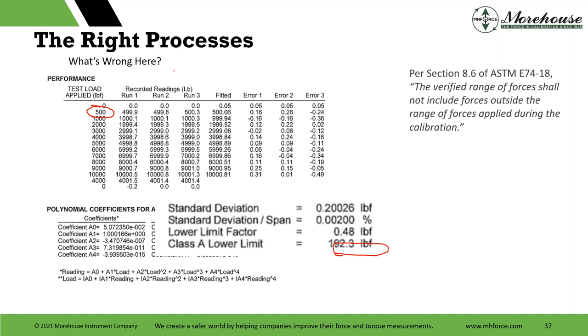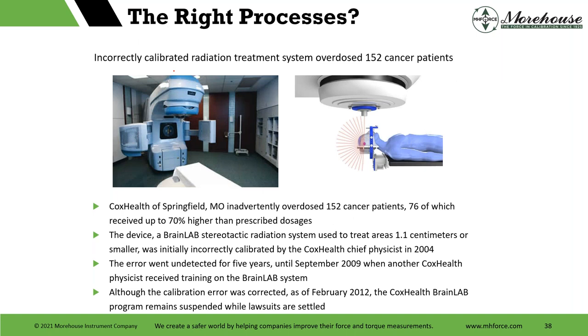Somebody reads the standard, doesn't fully know it, a customer asks them to make a calibration in accordance with it, and all of a sudden they do things they don't know any better. So here at Cox Health: 152 cancer patients, 76 of which received up to 70% higher than prescribed dosages. This was a BrainLab stereotactic radiation system used to treat tumors 1.1 centimeters or smaller, and it was initially incorrectly calibrated by Cox Health's chief physicist. The error went undetected for five years until somebody else received proper training.